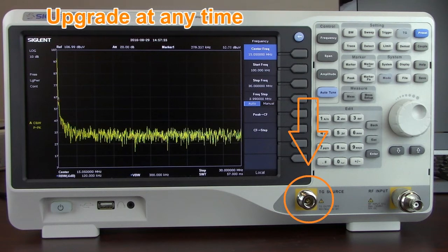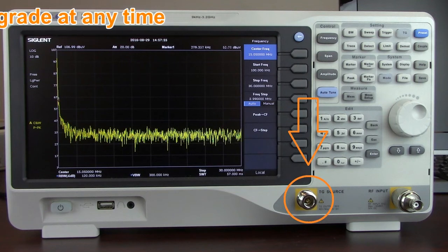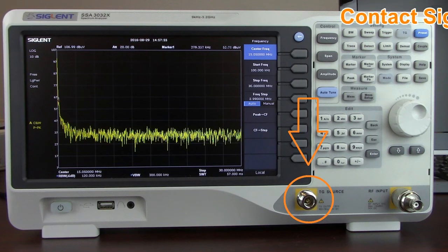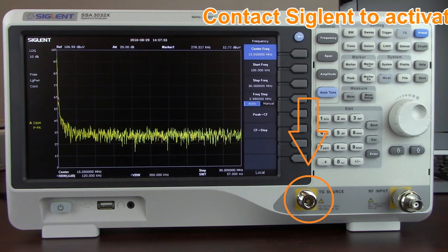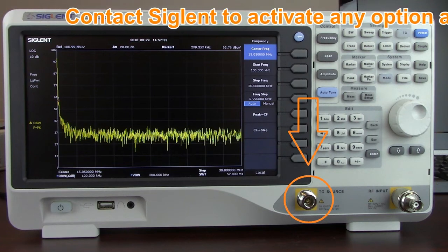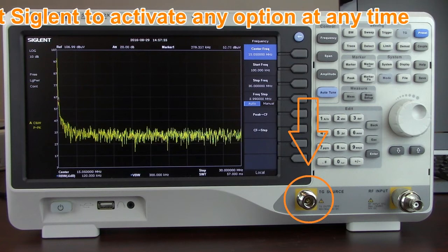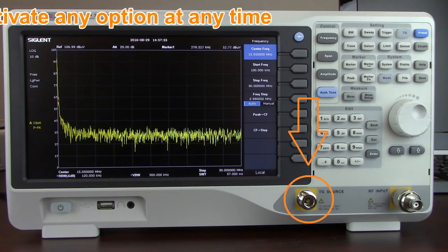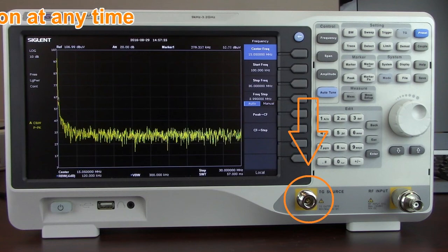Unlike many analyzers, the TG also operates to the maximum frequency of the instrument, not just to 1 GHz. So if you have a 2.1 GHz unit, the tracking generator operates up to 2.1 GHz. That makes the TG option even more powerful, giving you a full bandwidth capability, or full frequency span capability to test your passive and active devices.